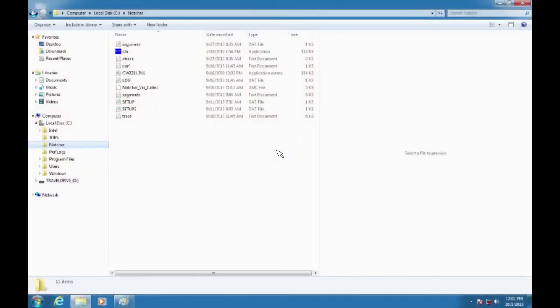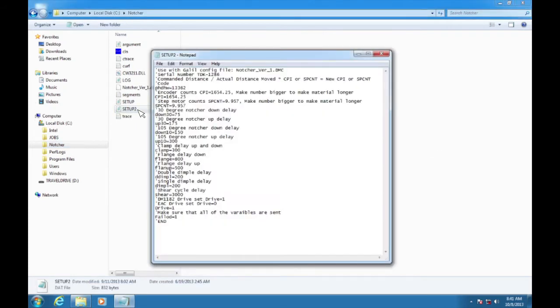Now that we've just made our move and we found out that the material is moving 47 3/4 inches, we have to go into Setup 2 and make a correction to our CPI value. In order to do this, we're going to have to do some math. What you want to do is take your commanded distance and divide it by your actual distance that the material moved and multiply that by your current CPI value.